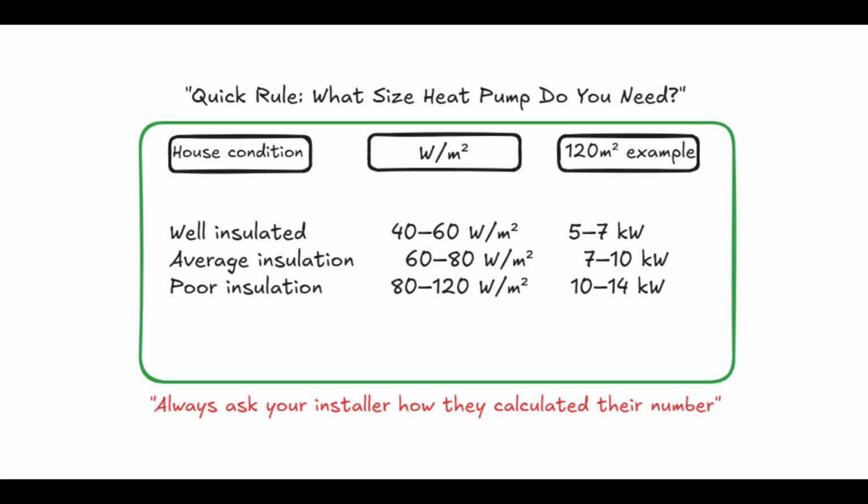In the last video, I promised to show you how a heat loss calculation works. Here's why it matters. If your installer sizes your heat pump based on square footage alone, you will end up with the wrong system, not slightly wrong, fundamentally wrong, and you won't find out until your first cold January when the system can't keep up. So let's fix that before you sign anything.